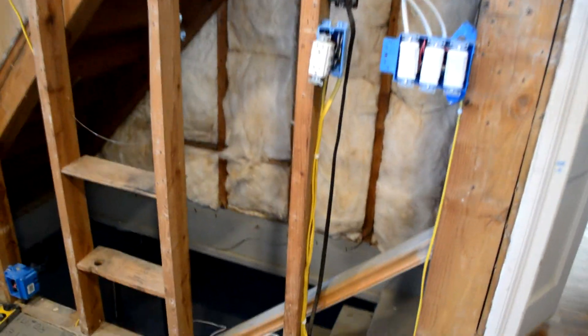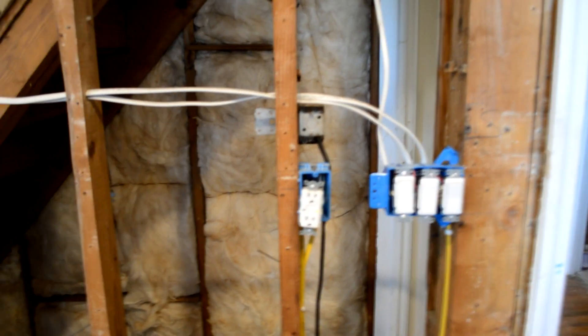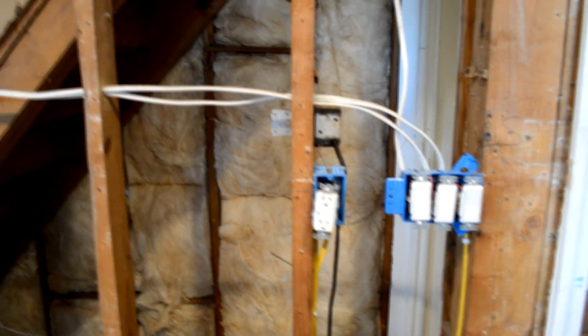That yellow wire coming to the box with the little duct is a GFCI outlet. This will help prevent any type of issue — a short, water damage, whatever can cause a problem — this outlet will stop it right there. If you have a lot of outlets in your kitchen — and this is a really small kitchen — you have to have at least two GFCI outlets. In this case we just have four outlets and I'm powering all of them with 12 gauge wiring.